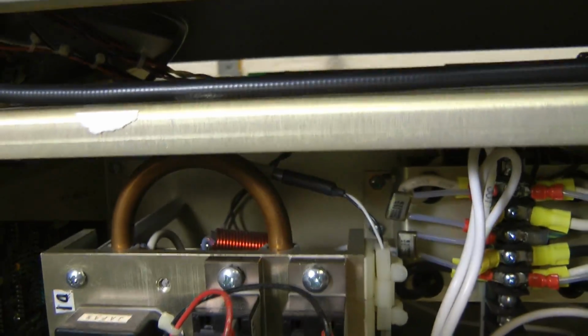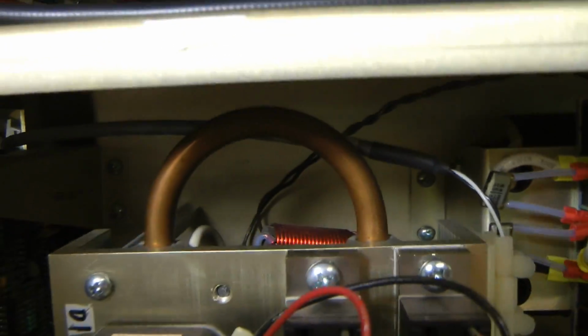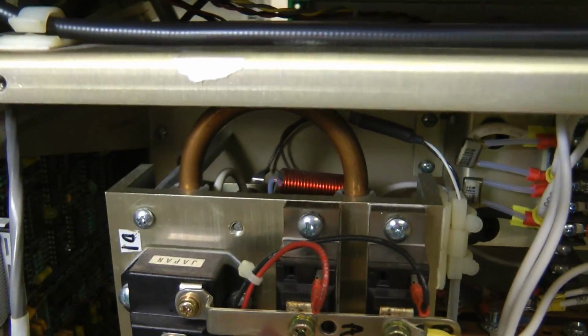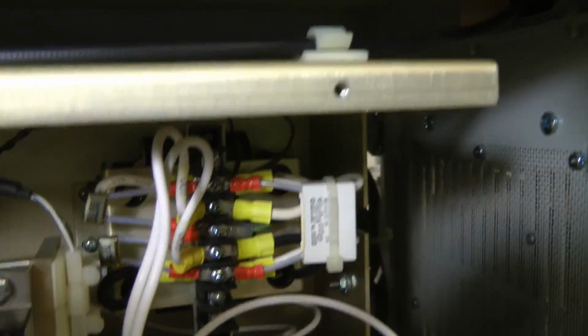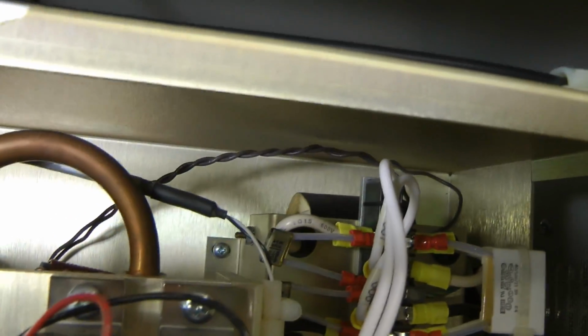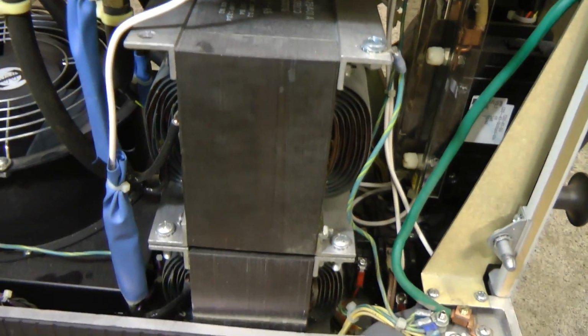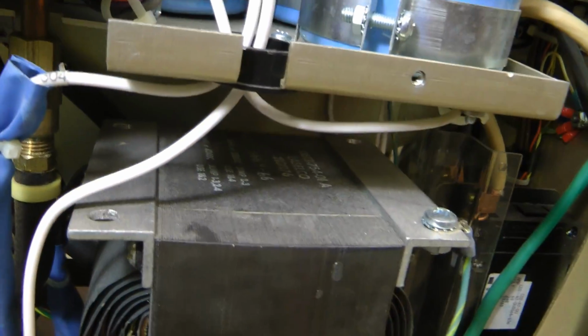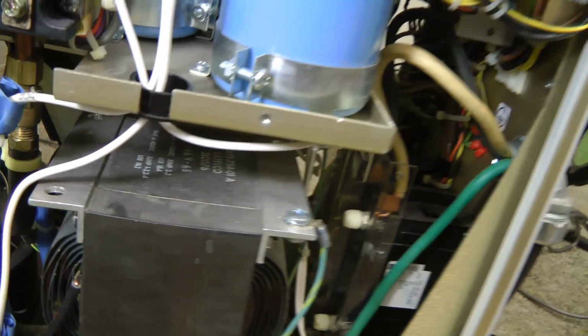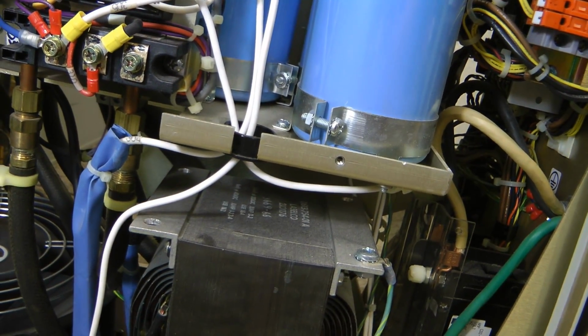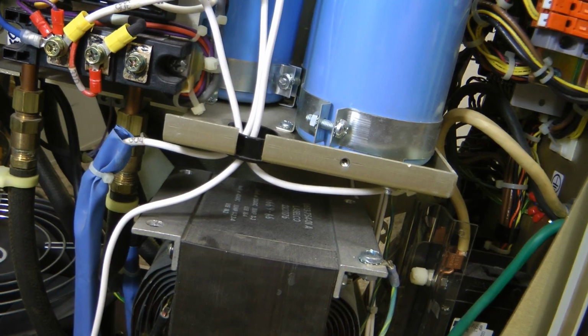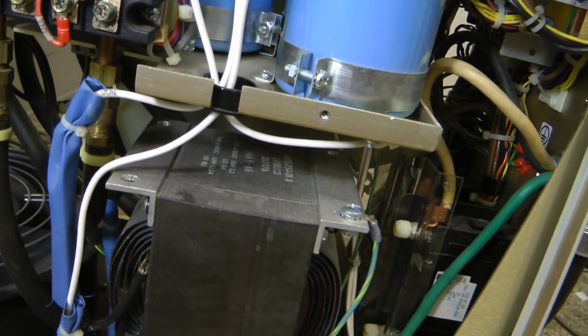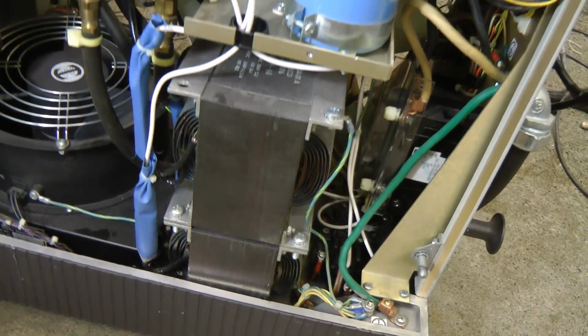Ooh, this back panel here is water cooled. You can see a pipe that runs down it, and then the lines run off there. And behind it there's more stuff. I see some fuses, some inductors. There's some sort of coil thing back there. And these things, which I thought were transformers earlier, are actually inductors, because it says on top of them 20 amps, 24 millihenry at 20 amps, or 6 millihenry at 40 amps, depending on how they're wired, I guess series or parallel.